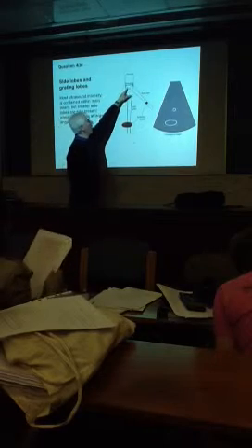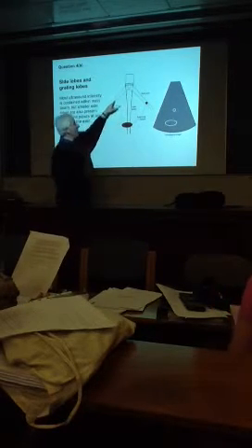In a poorly designed transducer, the physics of ultrasound beams enables some ultrasound power to go off at very specific angles to that main beam. These are known as side lobes. A well-designed transducer will make the intensity in those side lobes as low as possible. It's never exactly zero, but it can be designed such that it's almost negligible.